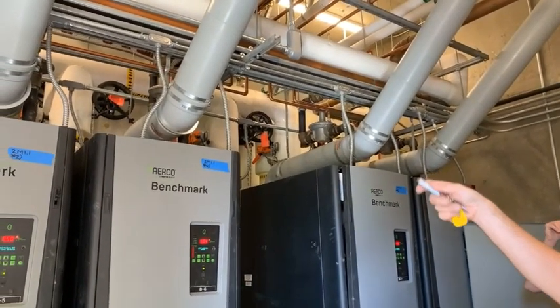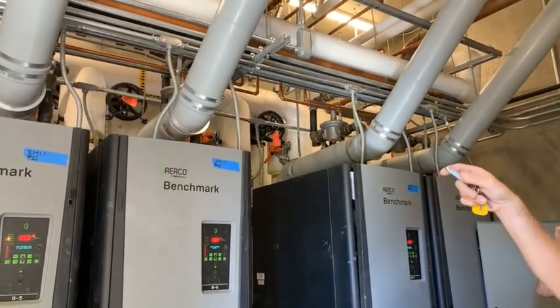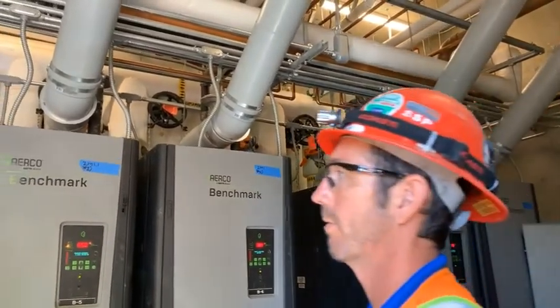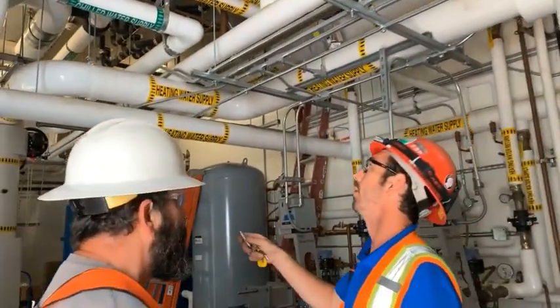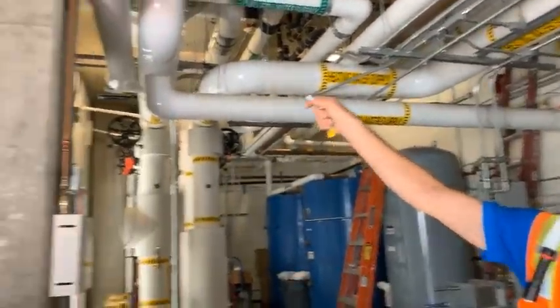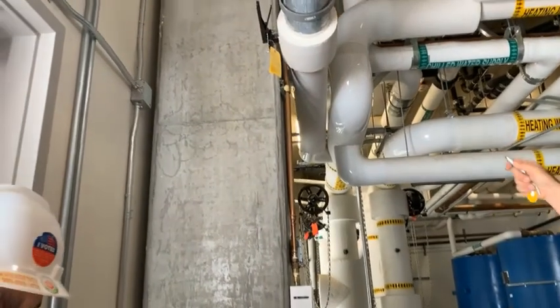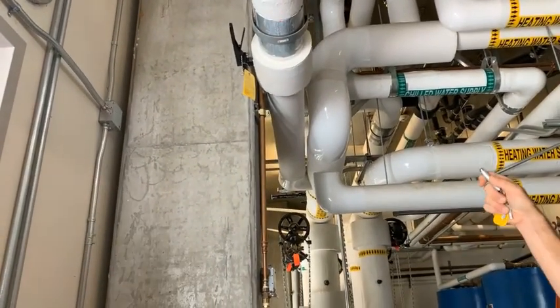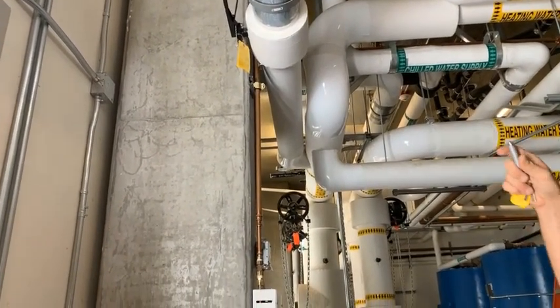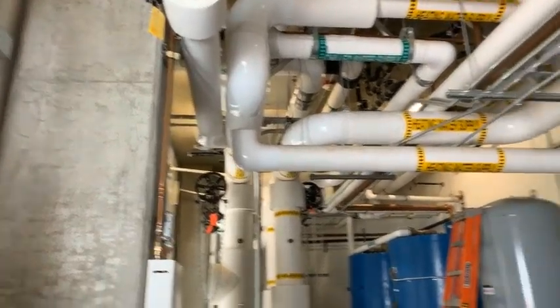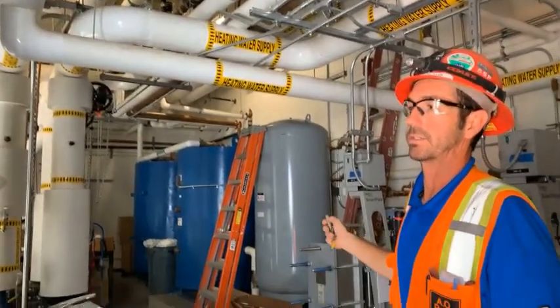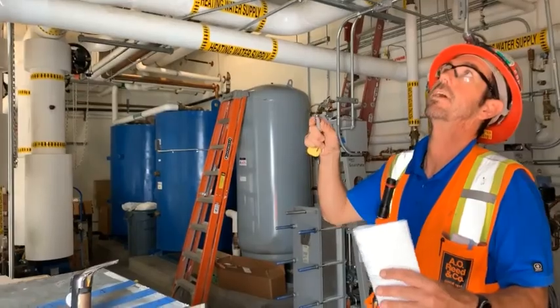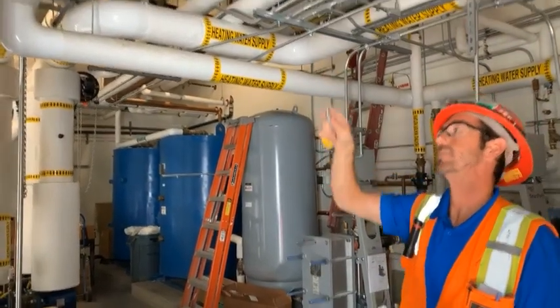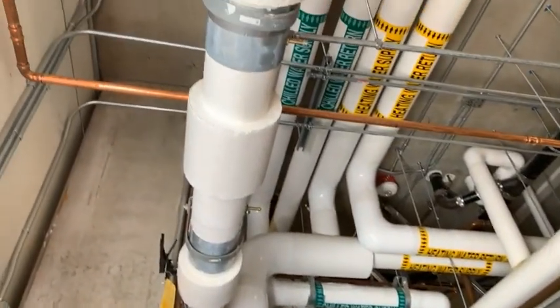Every boiler has its shut-off valve, strainer over here, the control valves. Like I said, this building is the same. We'll just go over the quick layout of all the stuff over here. I did forget to tell you that on the heating hot water over there too, there's a bypass line for a minimum flow for the boilers, okay? When we do heat exchanger training, I'll show you there's kind of two ways to create that low flow. There's this bypass line, or there's a three-way down here on the heat exchangers.